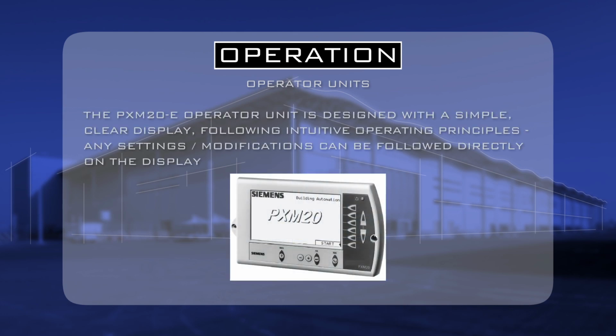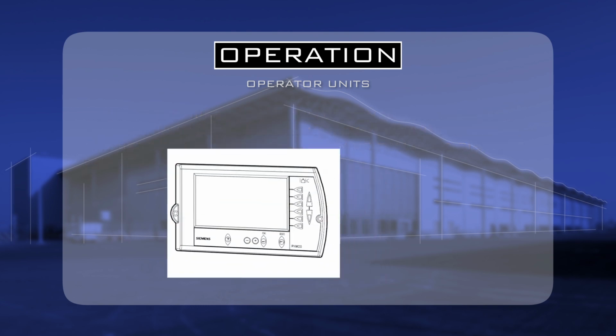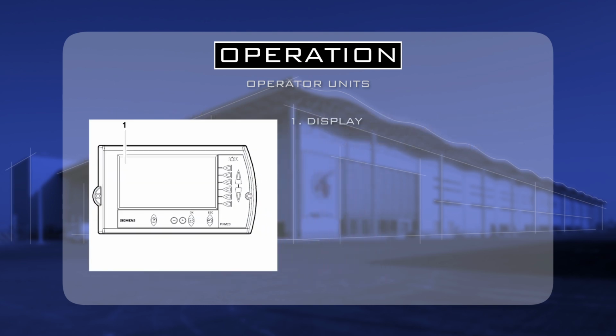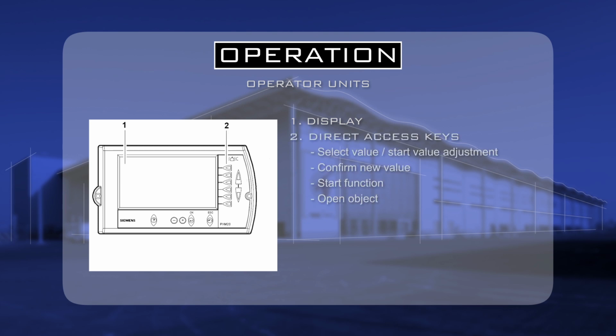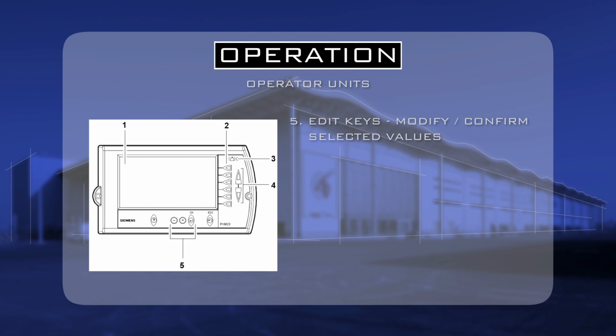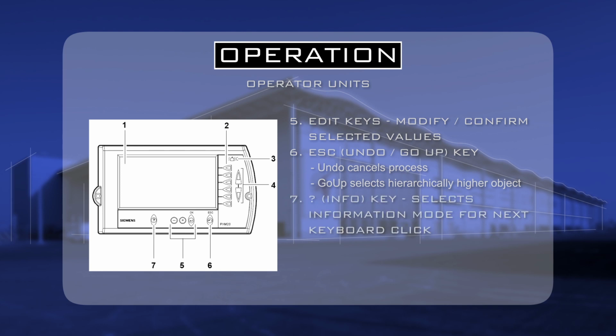The PXM20E operator unit is designed with a simple, clear display. It follows intuitive operating principles, and any settings or modifications can be followed directly on the display. Number 1 on the diagram points to the display. 2 points to the direct access keys. 3 is the alarm LED, which signals an alarm in the system. 4 points to the page up and down keys. 5 are the edit keys, which modify or confirm selected values. 6 is escape or undo or the go up key. 7 is the info key, which selects the information mode for the next keyboard click.